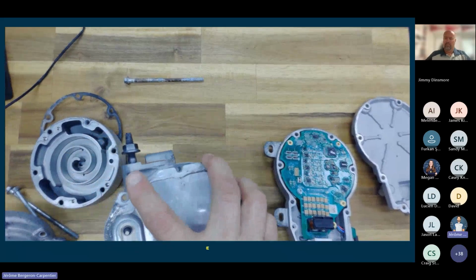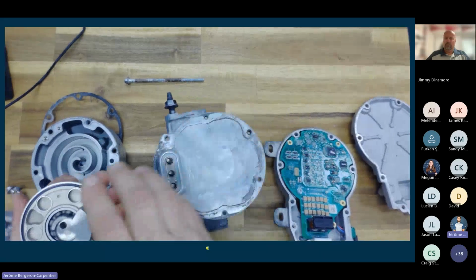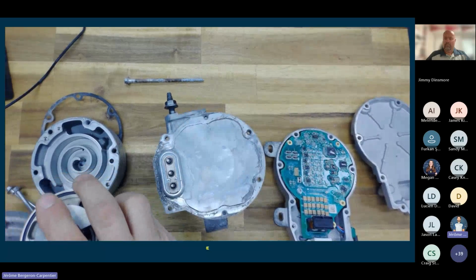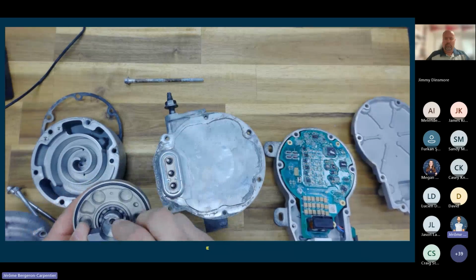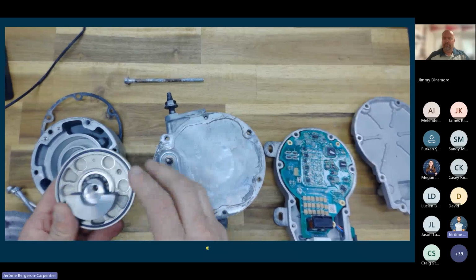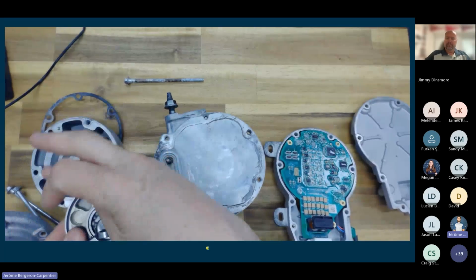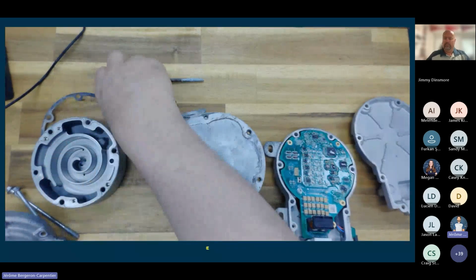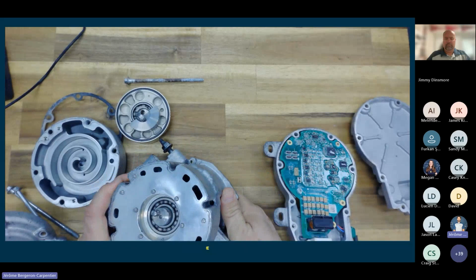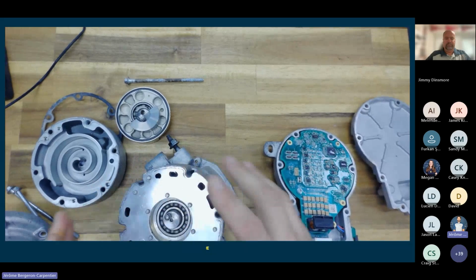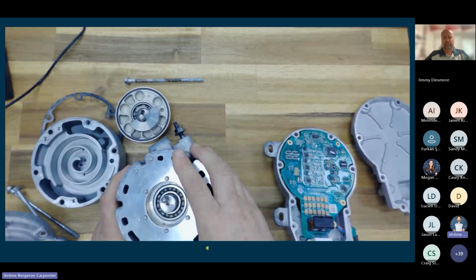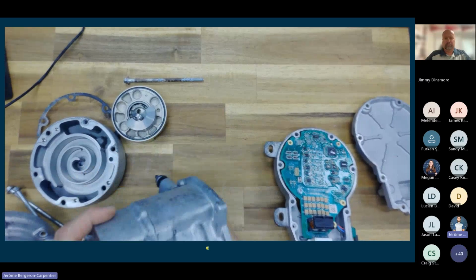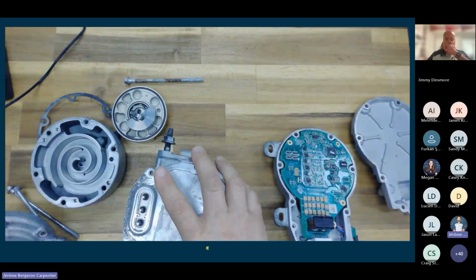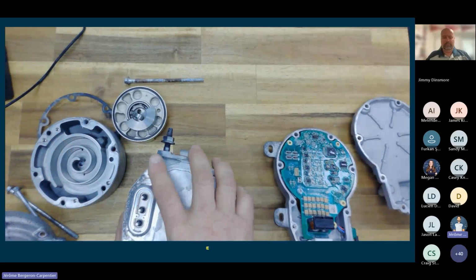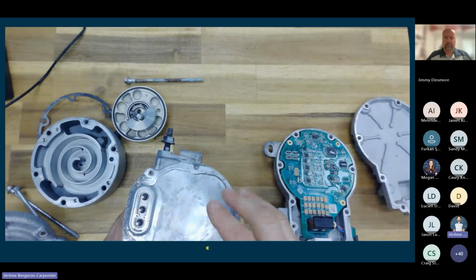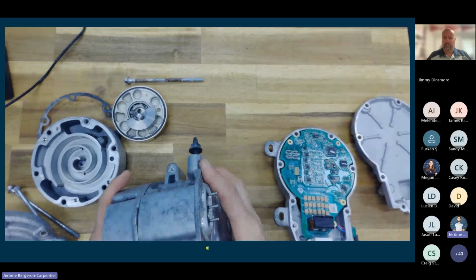I'm going to take this and flip this one over. And inside here, we see there's our counterweight, and there's another counterweight on the rotor itself. We'll see that in a second. We have our standard bushings on top here. They actually come out, you'll see them there. So our standard bushings ride on the shaft that rotates that scroll. As this thing turns, we have rotation within the scroll, which actually operates it. So let's go back into the electronic side, because this is pretty standard. It's taking low pressure and making high pressure by superheating that refrigerant before it goes into the condenser, whether it's inside or outside the vehicle, depending if it's a heat pump or not.